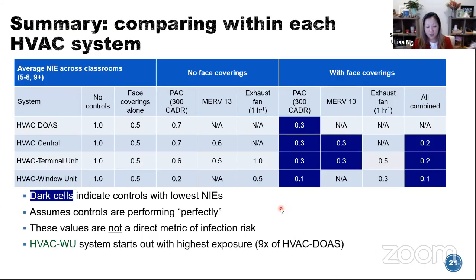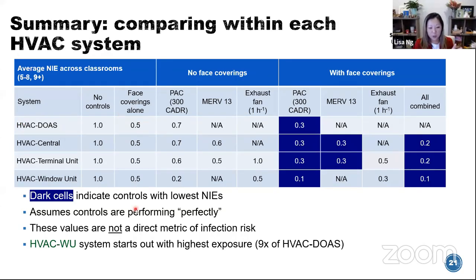There is a larger set of slides that we will publish when ready and after gathering more feedback. This slide shows individual controls and how much they reduce integrated exposure based on their respective system with no controls. For all systems, face coverings alone reduce the exposure to about 0.5. Here are individual controls without face coverings and their reduction in exposure, and here with face coverings. The combined portable air cleaner, MERV 13 filtration, and exhaust fan results depend on the system. These values are not a direct metric of infection risk, and even though the window unit system looks like it can achieve a normalized integrated exposure of just 0.1, remember it started with the highest integrated exposure compared to the central system.